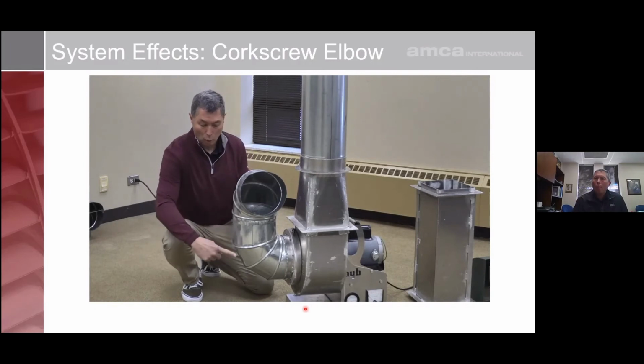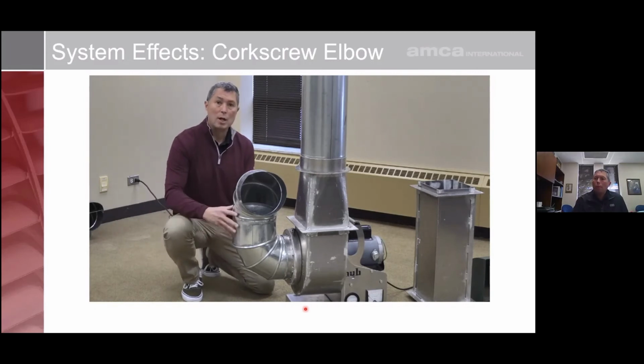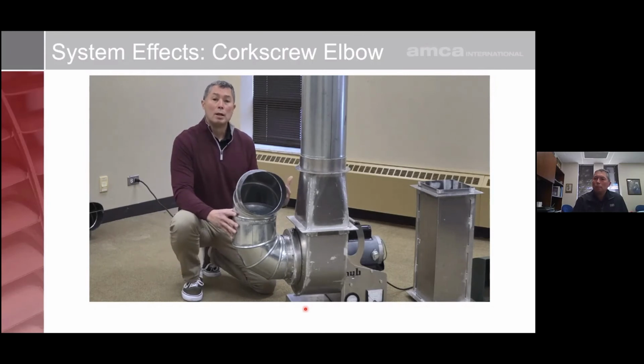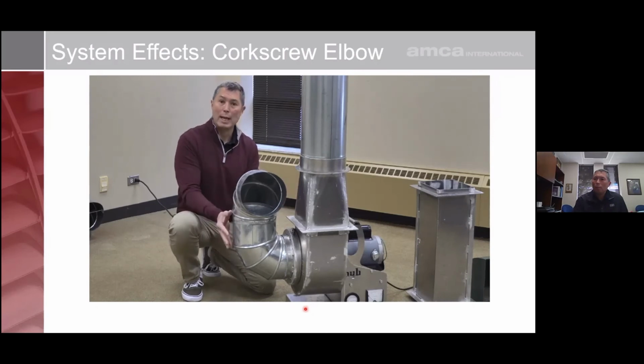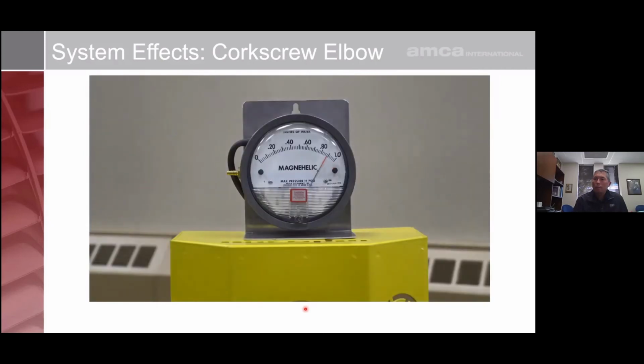It wants to go into the corkscrew, so it's starting to pre-spin as it goes through the fan. Pre-spinning of the air means that the air is going in the same direction that the wheel is rotating, and the air cannot get moved as efficiently as it would be if it was coming in straight and laminar. And that results in a fan that's quieter, but also when you look at the magnehelic gauge, you'll notice that the static pressure generated by the fan went down pretty significantly.